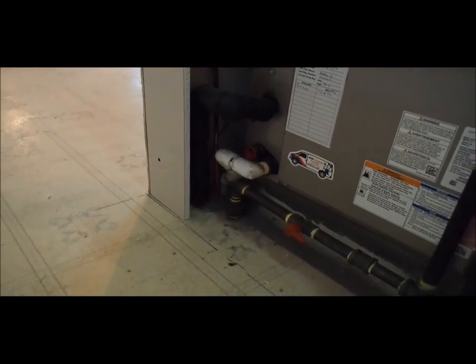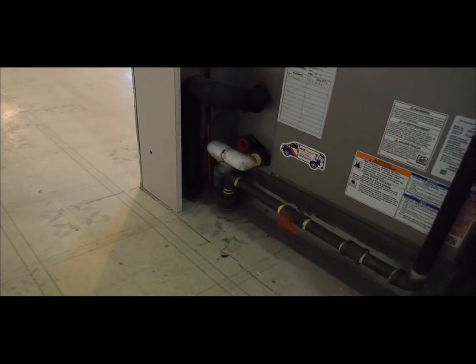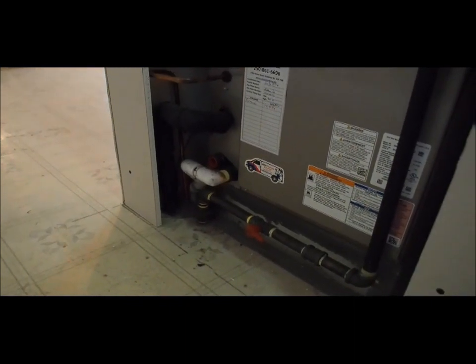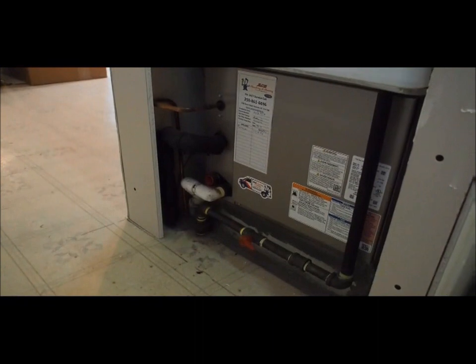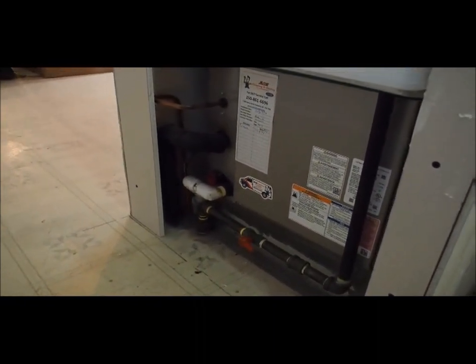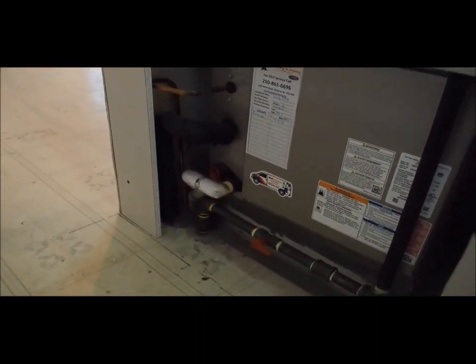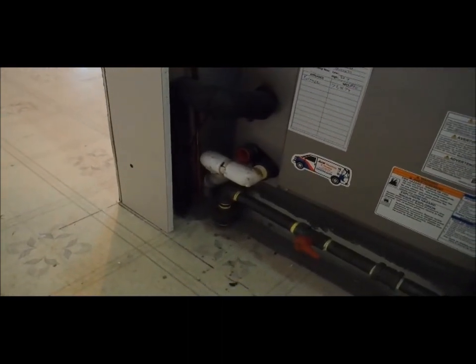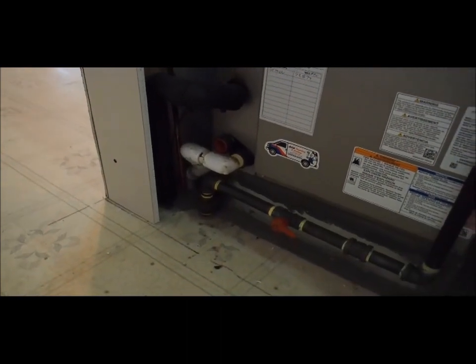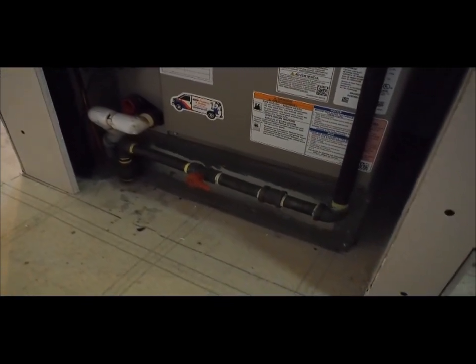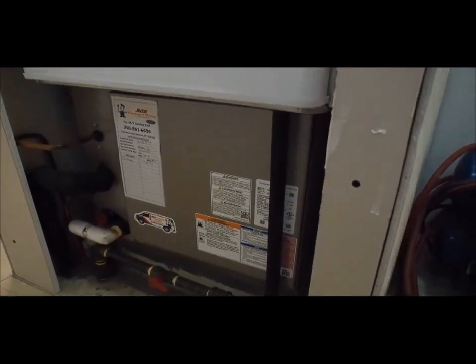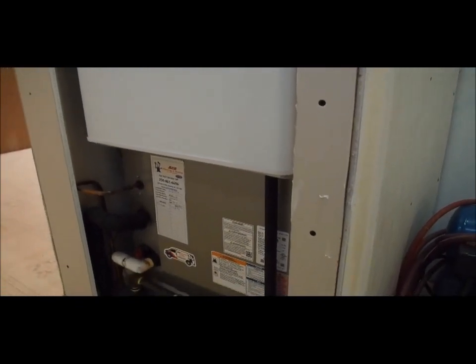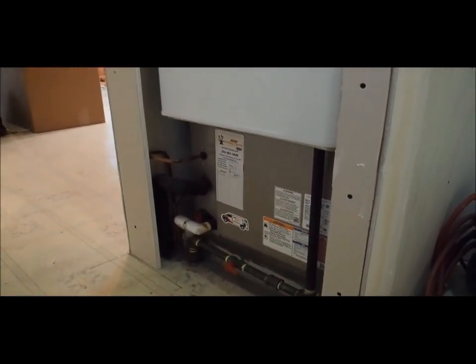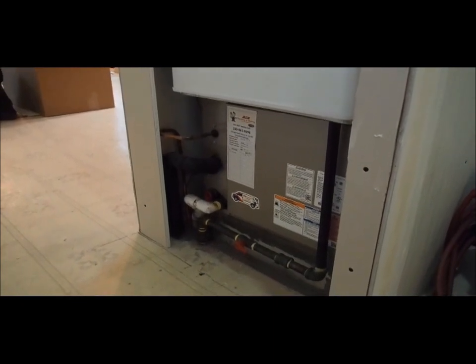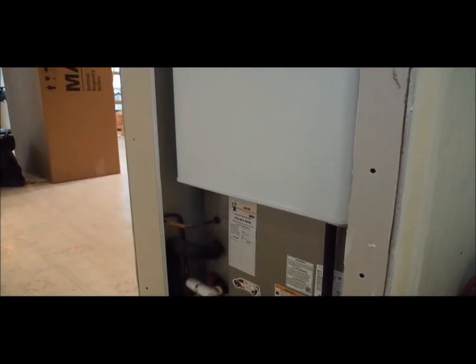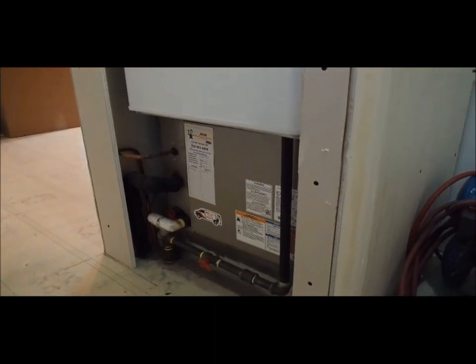That white tubing, that line there you see, is a drain for the condensate for the air conditioner. So as air is cooled, it creates moisture, and so that has to be taken care of. So that just goes down through the floor and out the bottom of the mobile home. So down here we have the gas line, and you can see that little red valve there. This is a natural gas furnace in here. So by doing this hybrid thing here, it's not really a hybrid, but us using the two brands, what that did for us is saved us about $1,000.